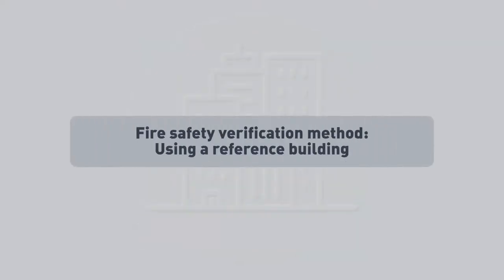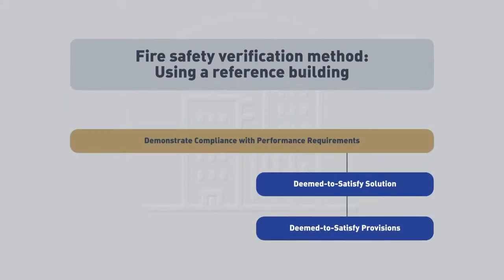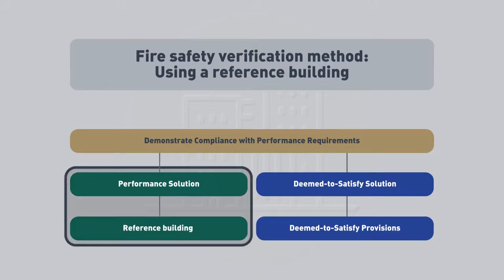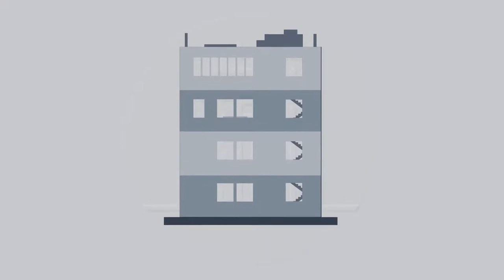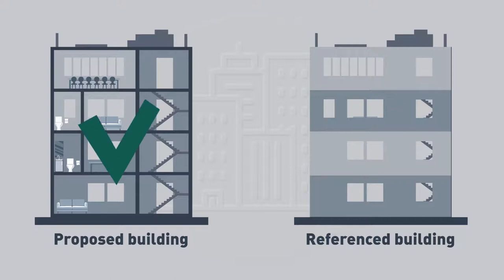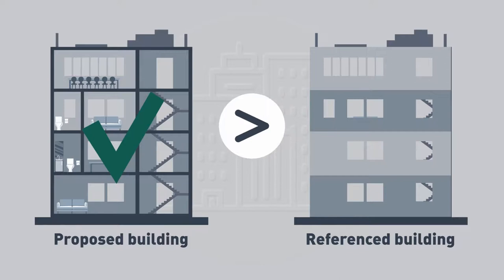All scenarios need to be compared to a reference building that complies fully with the DTS provisions, to verify that the proposed performance solution complies with the relevant performance requirements through equivalence with the DTS provisions. The design of the reference building should be as close as possible to that of the actual proposed building that the verification method is being applied to, and in full compliance with the DTS provisions. The performance solution for the proposed building needs to be equal to or better than the DTS-compliant reference building, providing a benchmark for comparing the performance solutions being verified.